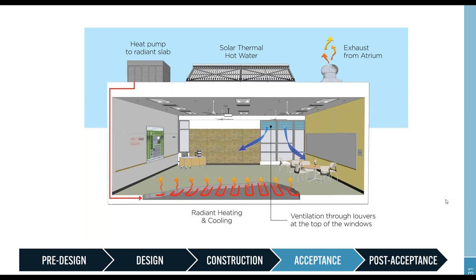On top of that, we had natural ventilation terminals that were out of control. They would only open once the room had gotten stuffy, and not provide ventilation when the room was just comfortable. And this just became a headache right from the beginning. So our team got involved in this project that, as I said, had already been in operation for over a year. And all these headaches, all these energy costs, all of these issues from a building that was supposed to be net zero, from a building that had gone through the LEED system in order to be a platinum project. So without the missing pieces of commissioning, this project just was not workable.